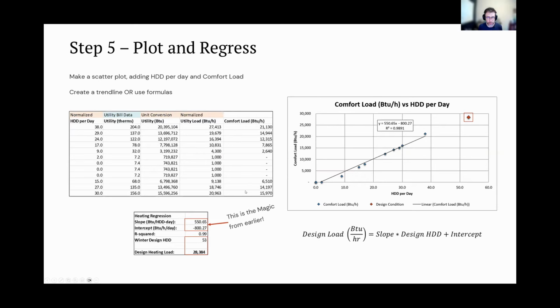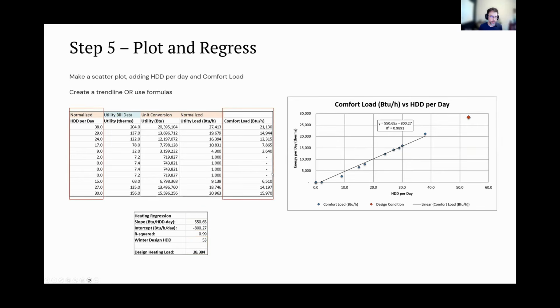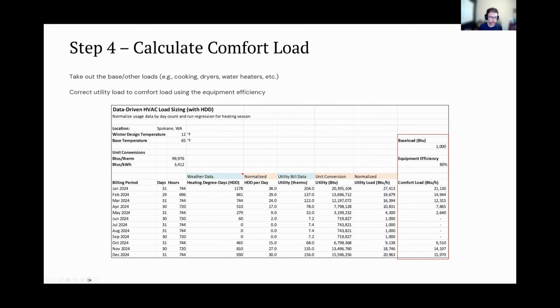Remember I was talking about the magic earlier—this is the magic. We're going to do the math a little differently: we take the slope and multiply it by our design heating degree days, which I've calculated here as 53. I forgot what the design load is—yeah, the design temp for this, I did this for Spokane, Washington, so the design temp there is 12 degrees.